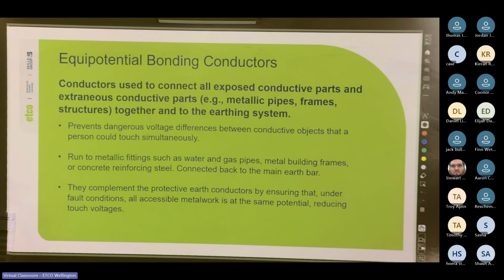Yeah, it ensures that all metalwork is at the same potential, and in the event of a fault to a piece of external metal that's bonded, it'll create a path through the earth back to the earth bar, through the MEN link to the neutral, and allow our circuit protection to trip.